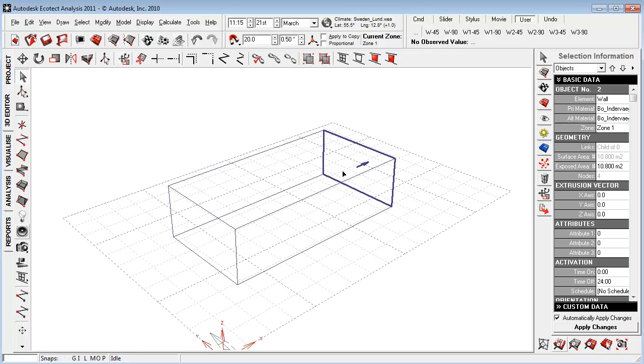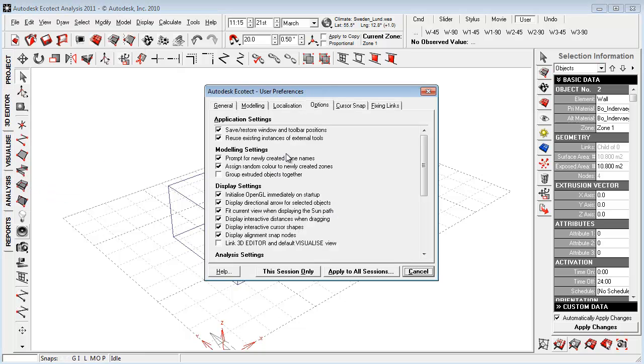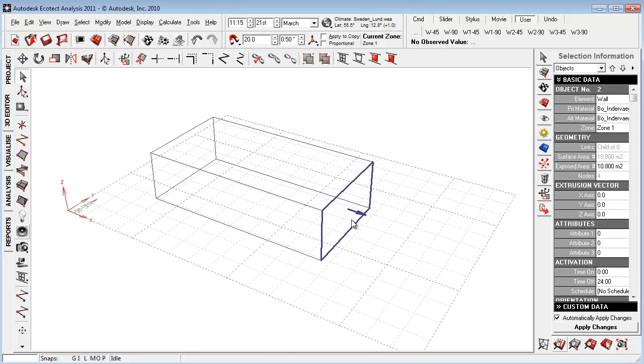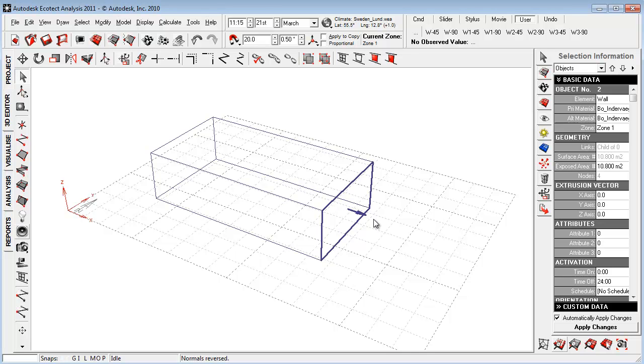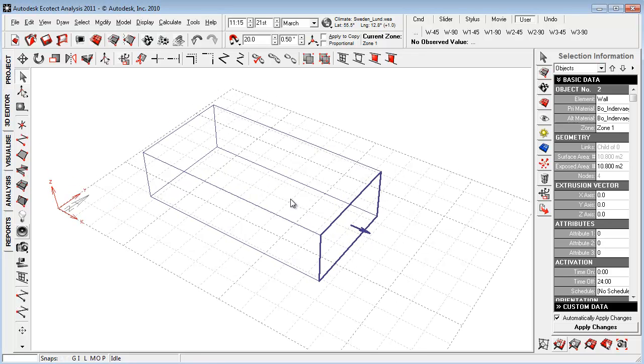If you want to display this directional arrow, go to File, User Preferences, Options, and say Display Directional Arrow for Selected Objects. You can now see that this arrow should always point from the inside to the outside, which is very important. If you want to flip it, just hit Ctrl-R to flip the surface normal. This is very important because Ecotect assumes that the temperature inside a room will always tend to align with the outside temperature.